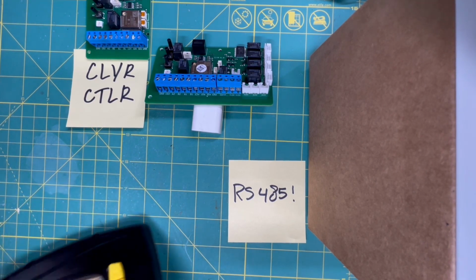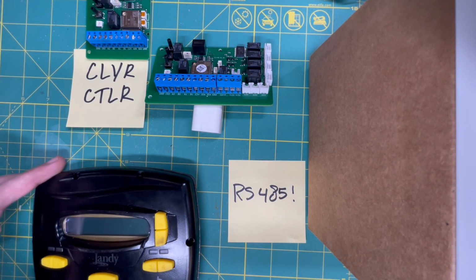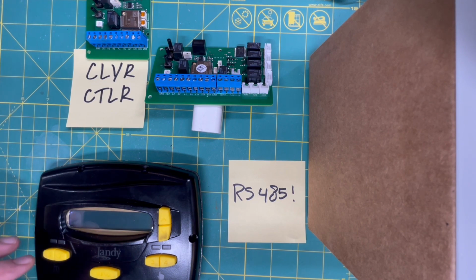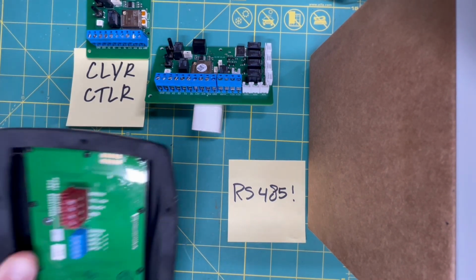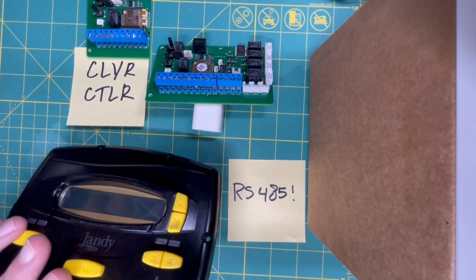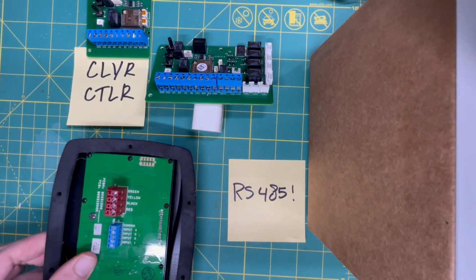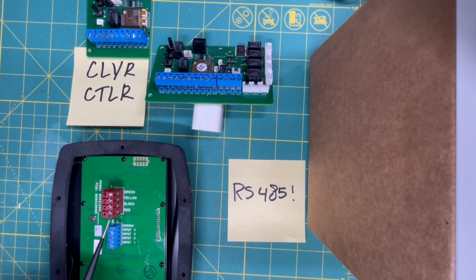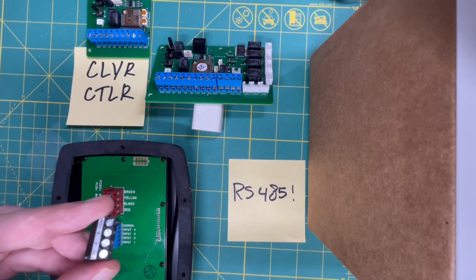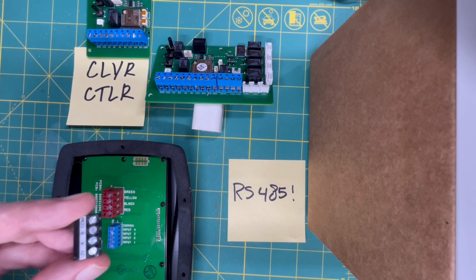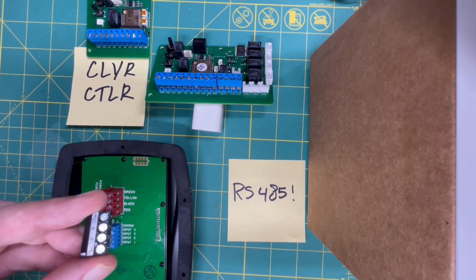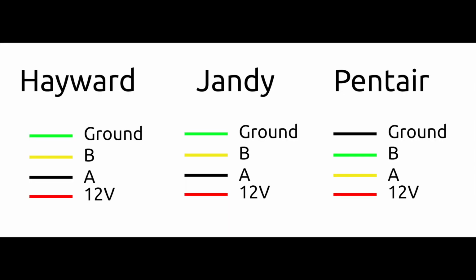Every piece of equipment from Jandy, Hayward, Pentair, and others typically comes with a 4-port terminal. Here's a Jandy pump screen that's been removed. If you flip it over, there's a red 4-port terminal marked red, black, yellow, and green. Some vendors designate by color, but unlike Jandy, this Hayward plug from a pump shows markings of 12 volts, A, B, and COM. So these vary from vendor to vendor.